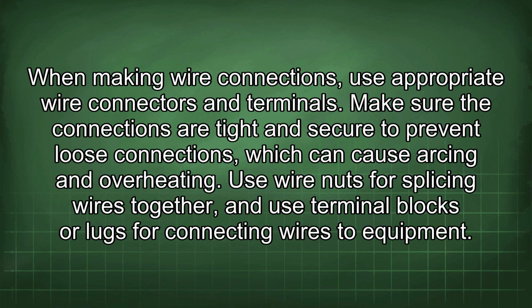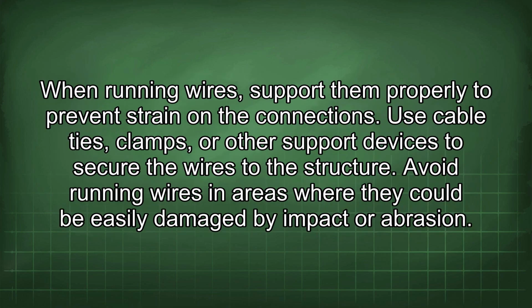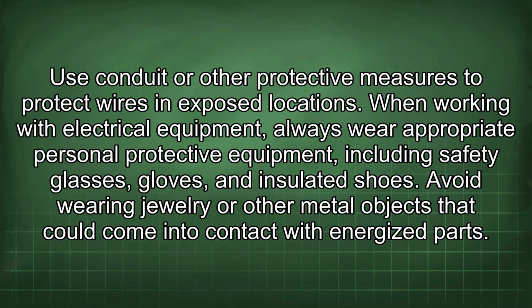When making wire connections, use appropriate wire connectors and terminals. Make sure the connections are tight and secure to prevent loose connections, which can cause arcing and overheating. Use wire nuts for splicing wires together, and use terminal blocks or lugs for connecting wires to equipment. When running wires, support them properly to prevent strain on the connections. Use cable ties, clamps, or other support devices to secure the wires to the structure. Avoid running wires in areas where they could be easily damaged by impact or abrasion. Use conduit or other protective measures to protect wires in exposed locations.